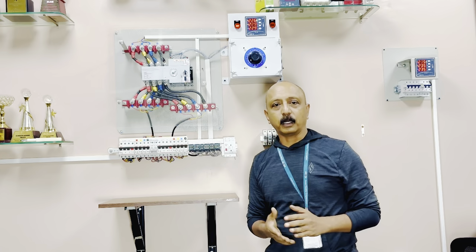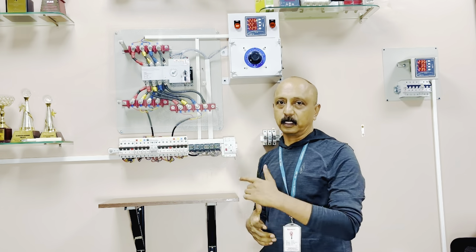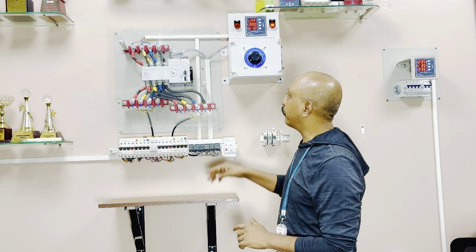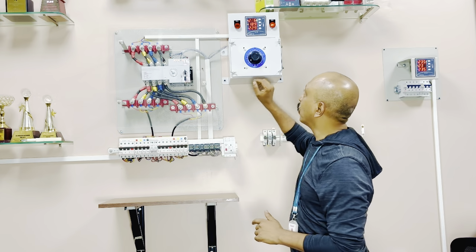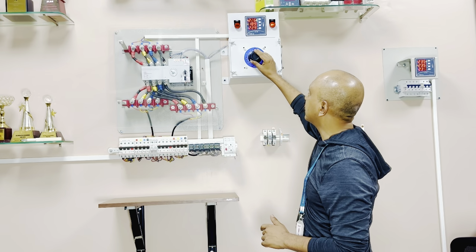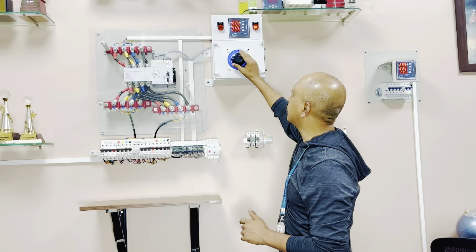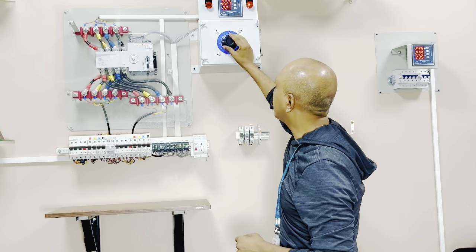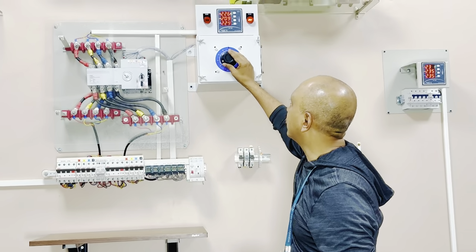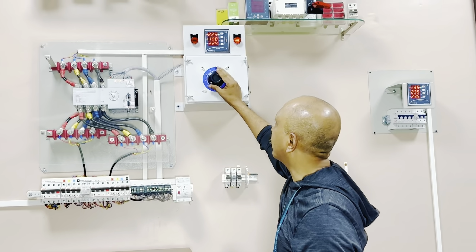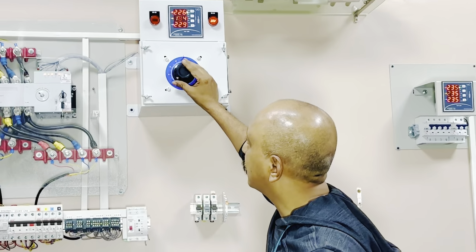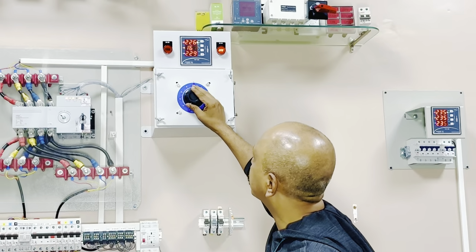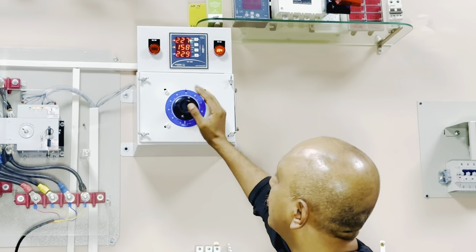I will now take you to the under voltage protection, which is inbuilt in the ATS. The ATS is in source 1. We have an auto transformer where we can reduce and increase the voltage. Typically 230 is the phase voltage. I'm taking it down now, let's say to 160 volts, where the threshold level of the under voltage is programmed for 160 volts.